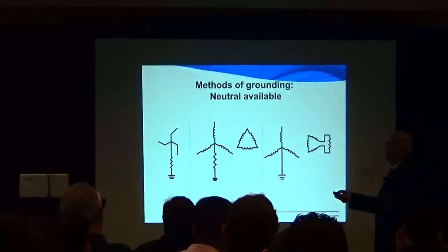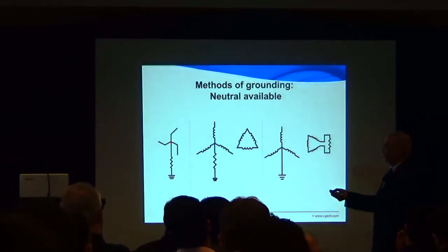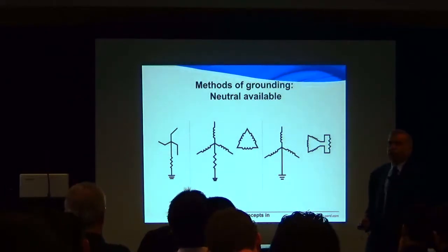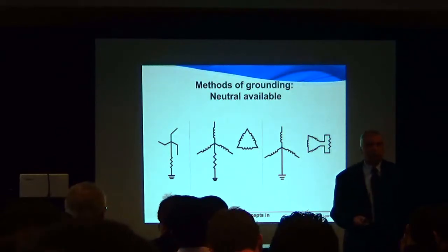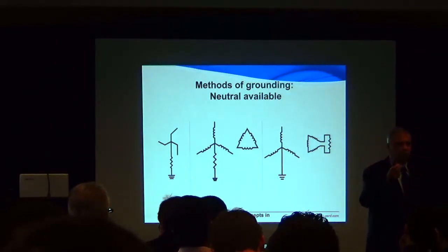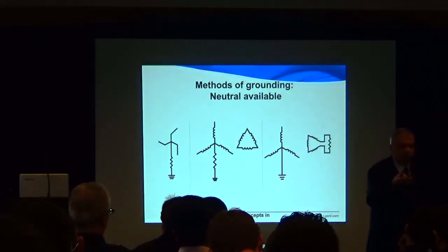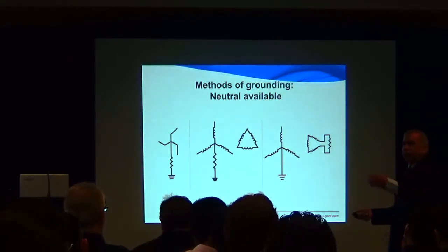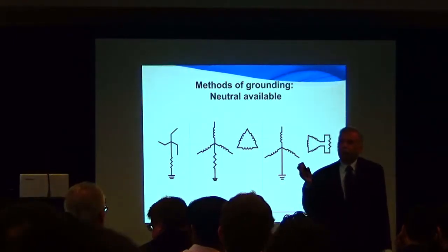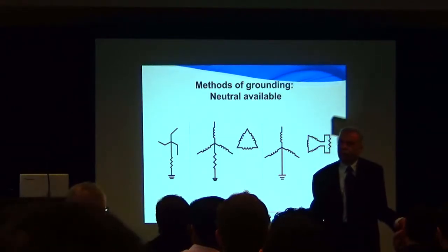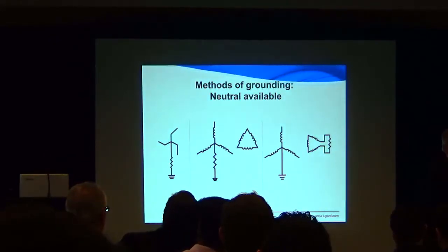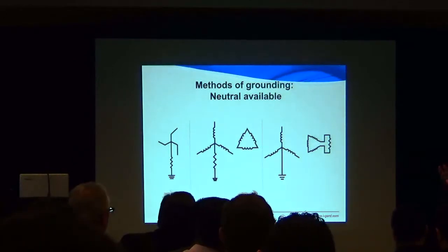So this is a zigzag auto transformer that provides a neutral point that allows you to take that to the ground. This transformer's size and value is controlled by how much current you allow to flow. So if you are going to put 5 amperes through that resistor, then the size of that transformer is based only on the 5 amperes. So 347 times 5. But if you are going to have no resistor, as was the case with Bob here, who was saying I need an effectively grounded system, then the same zigzag can provide a low impedance ground path, because there isn't any other impedance. The transformer impedance is the only impedance. So you can use that zigzag as a grounding transformer right across the board, with or without the resistor. It depends on what your application is.